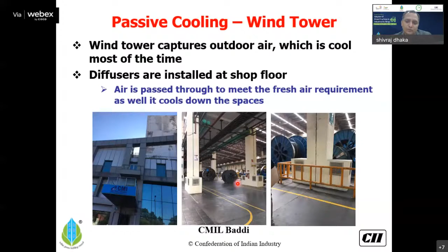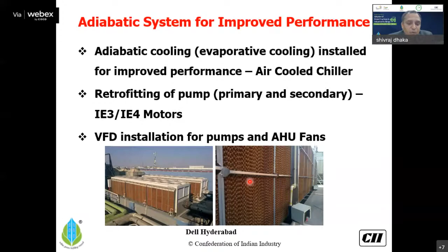Another example is, as and when there is some air conditioning requirement, a project can go ahead with adiabatic cooling. It is a very cheap solution compared to a water cooled chiller or so, but an air cooled chiller can work very well - it can have savings in kilowatts per ton from 0.98 to 0.82. That's how we have recorded this kind of performance in some good commercial buildings for adiabatic applications.